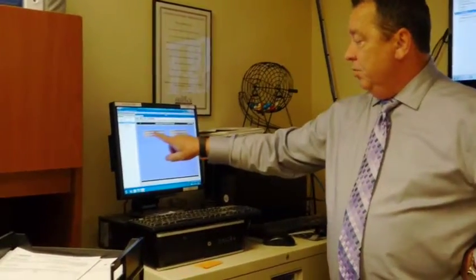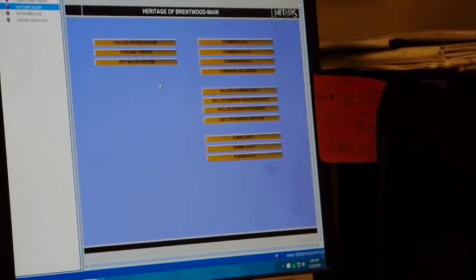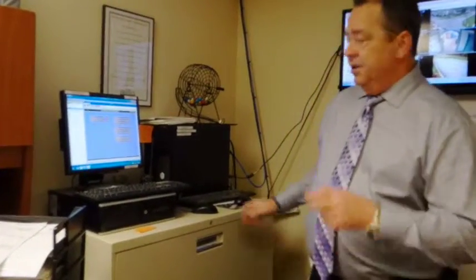Now, when you go back and you have the chilled water, cooling towers, and the hot water system, that is your system. But the system has to be one of two. It either has to be calling for heat or it has to be calling for air conditioning. We are not at that point to where we can allow somebody to have both at both times of the year. And that's why it's so important when the summer is here, humidity is unbelievable in Tennessee. You're looking sometimes the humidity's 50-60%. You can go out here and walk on it. It's so thick sometimes. But residents will have their air conditioning on in their homes. They will have the door and the windows wide open. That's a rainstorm waiting to happen right there. I mean, it's humidity unbelievably bad. And it causes the vents to leak, it streaks down the walls, it tears.